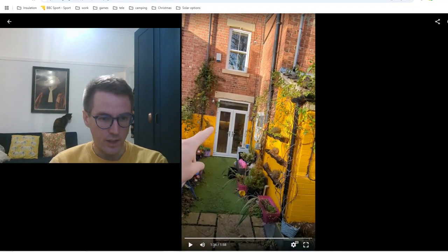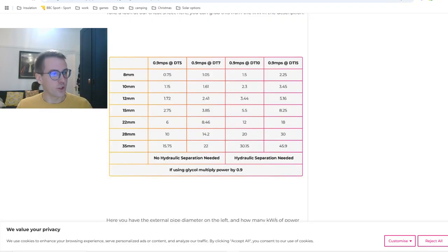Right, so let me just get something up that explains what I'm talking about here. Without being 100% jarring at all, here we are on the Heat Geek website with their heat cheat sheet for pump size. What I talked about in another video is that heat pumps and boilers work off different theories. A boiler wants to drop 20 degrees, or a DT of 20, and can have a lower flow rate. And so you can put in loads of heat.